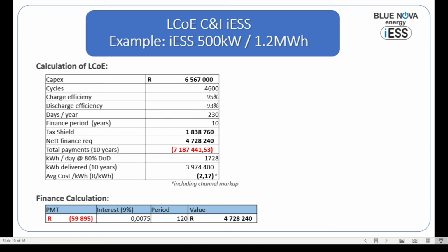If one looks at the sum of all the payments made over the 10-year period, that is a total of about 7.2 million rand that will have to be paid. And if one looks at the amount of energy that one can cycle per day, we're looking at about 1.7 megawatt hours. Those are the two controlled discharges at 80% DOD of this 1.2 megawatt hour storage device. So if you look at the total amount of kilowatt hours delivered in 10 years, it's about 3.9 million kilowatt hours, and that would then be at an average cost of about 2.17 rand per kilowatt hour cycled. That's the average cost over the 10-year period. If one looks at the bottom of the screen, at the finance calculation, the monthly repayment is roughly 60,000 rand, calculated at 9% on the finance portion of 4.7 million over the 10-year period. That is what will have to be paid off.